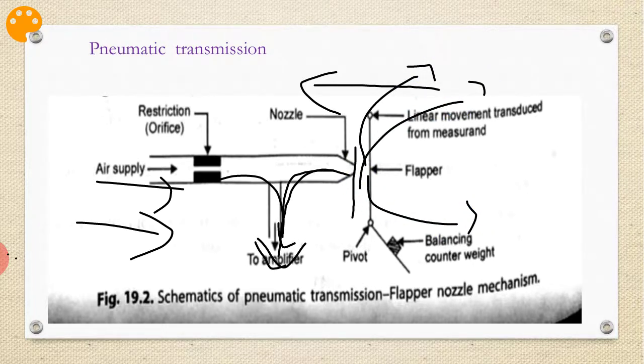Thus the movement of the flapper from one extreme position to another serves to control the amplifier, which produces an air pressure proportional to the measurement of adequate strength for transmission over the required distance. This is the basic schematic showing the pneumatic transmission flapper-nozzle mechanism.